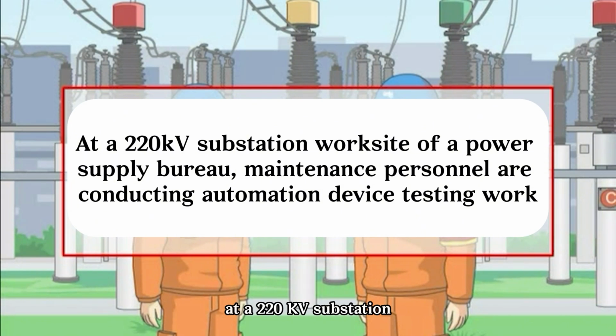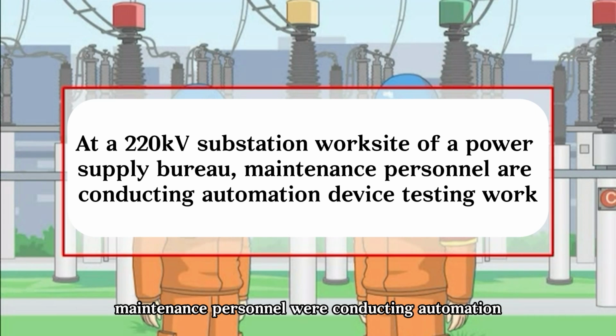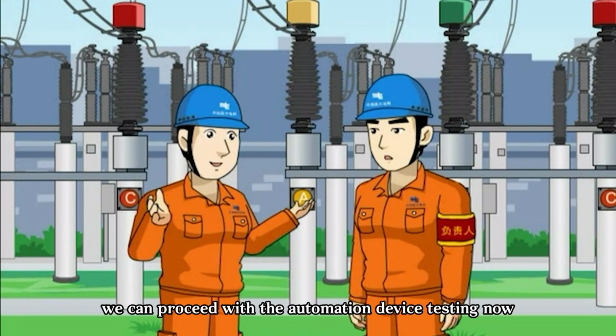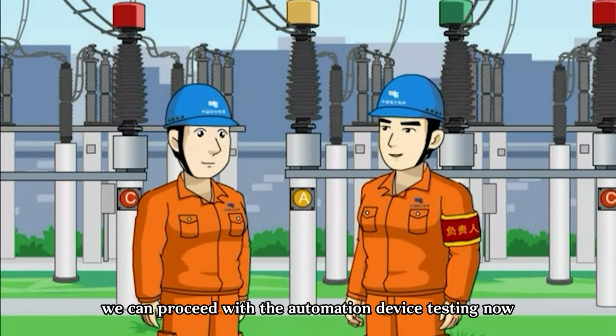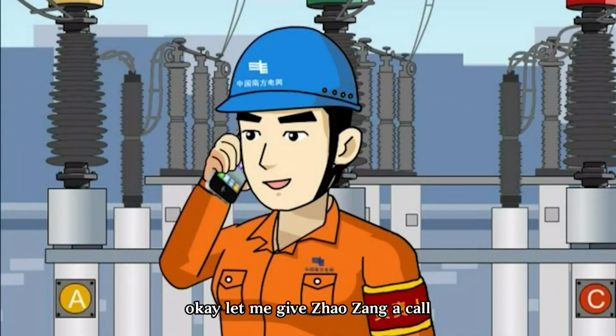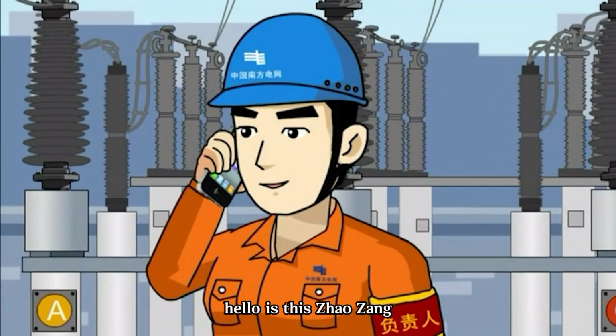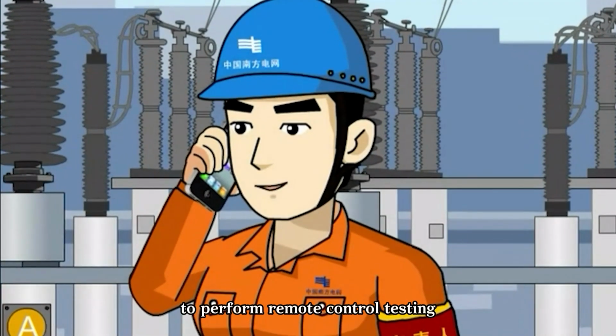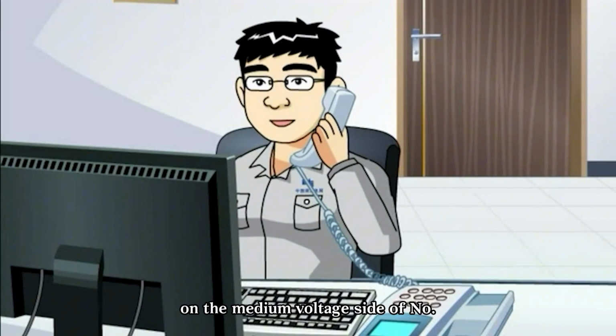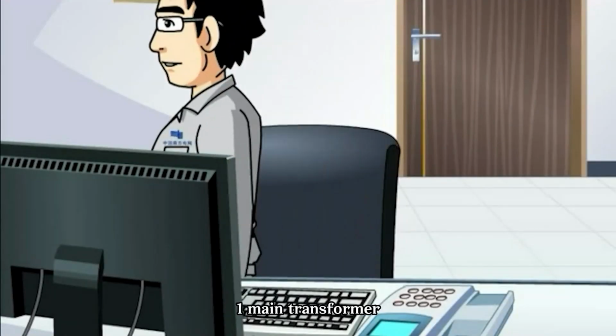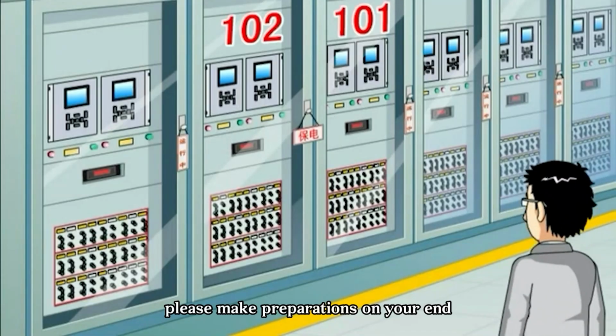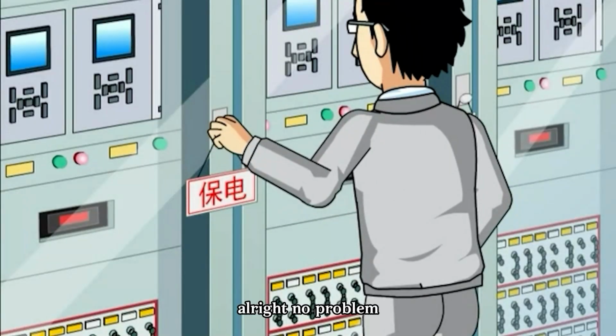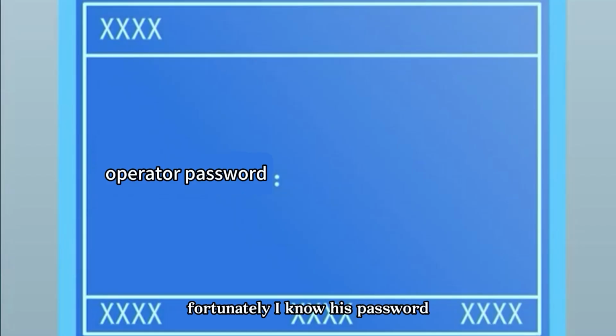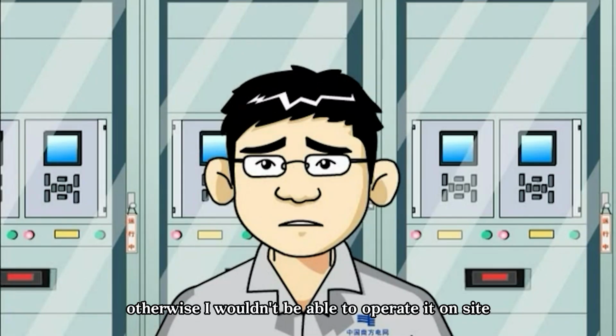At a 220 kV substation operation site of a power supply bureau, maintenance personnel were conducting automation device testing work. We can proceed with the automation device testing now. Okay, let me give Zhao Zhang a call. Hello, is this Zhao Zhang? We need your cooperation now to perform remote control testing on the 101 circuit breaker on the medium voltage side of number 1 main transformer. Please make preparations on your end. Alright, no problem. Old Zhu isn't here. Fortunately, I know his password, otherwise I wouldn't be able to operate it.